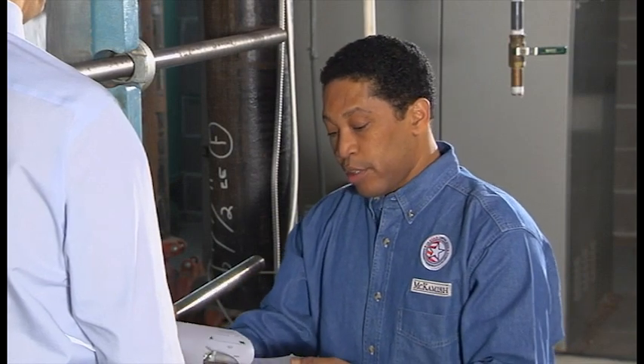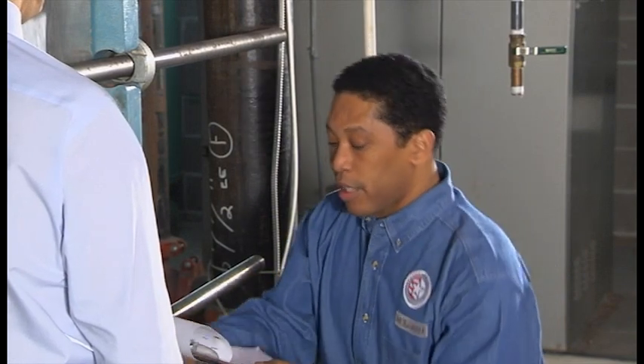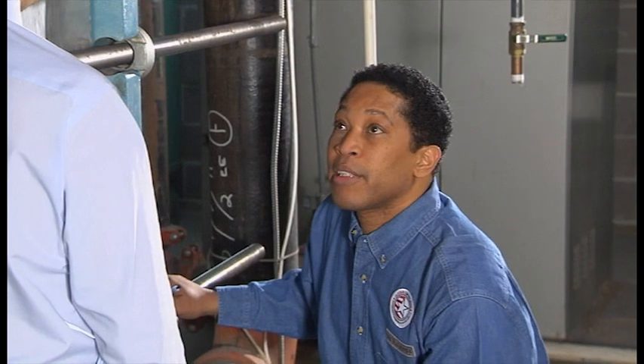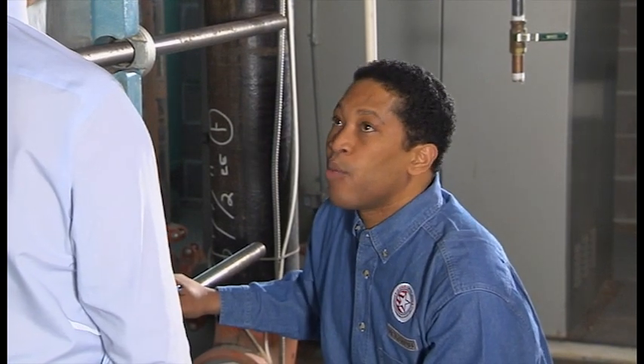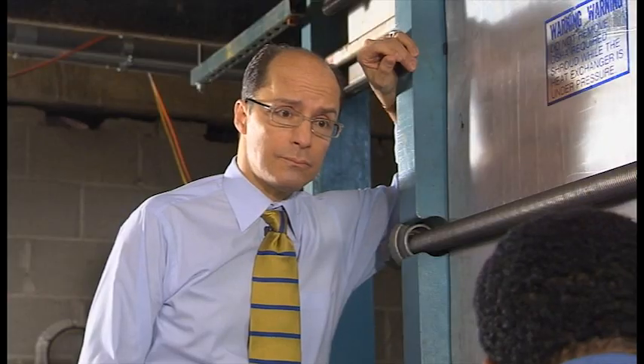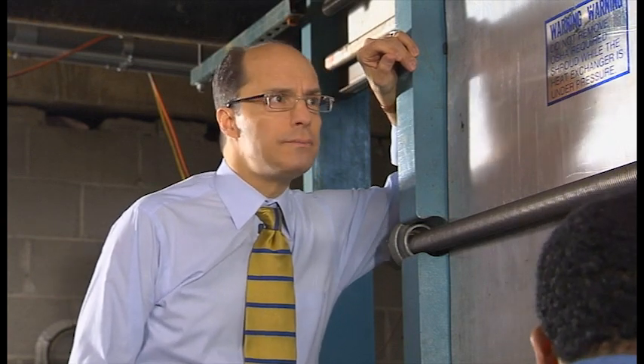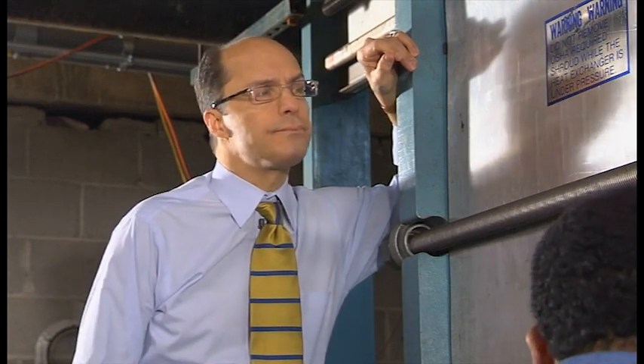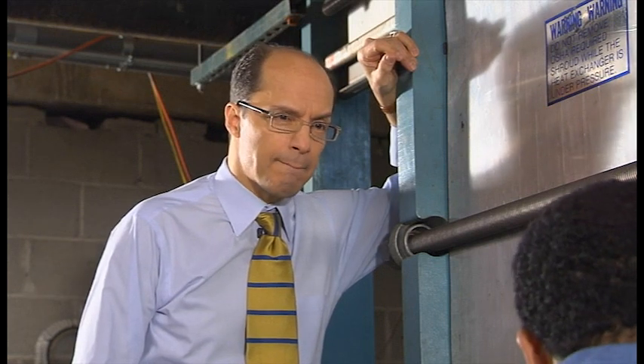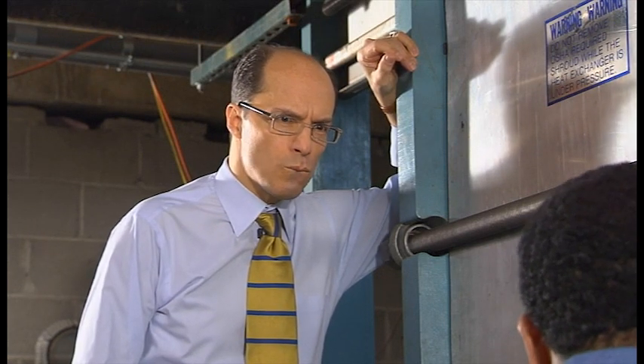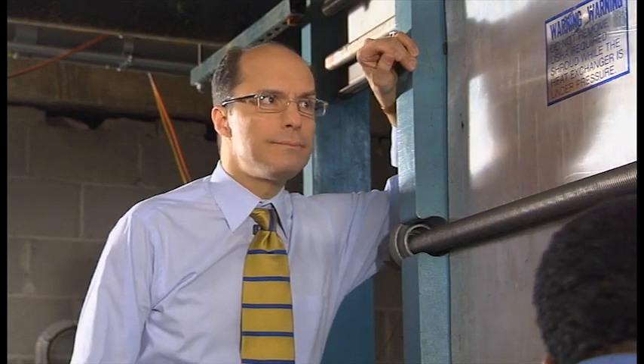Well, we can still schedule the repairs to the heat exchanger at a time that is more conducive to minimizing costs. But I wouldn't bypass the heat exchanger. It alters the integrity of the entire system, and if the high pressure safeties fail, it could actually cause the soft plugs release to open on the heat pump's refrigerant side, which creates a lot of safety and environmental hazards. And that's a liability that neither of us can afford to accept.